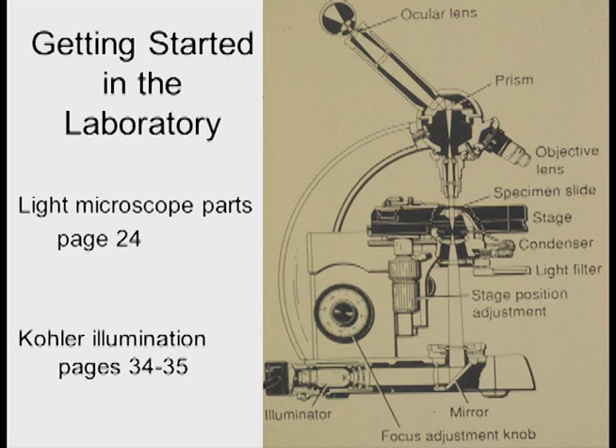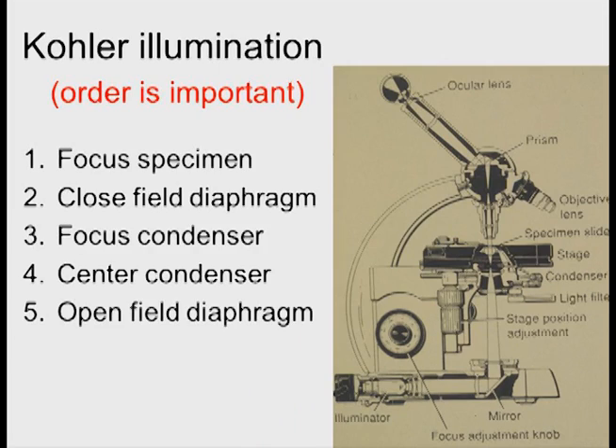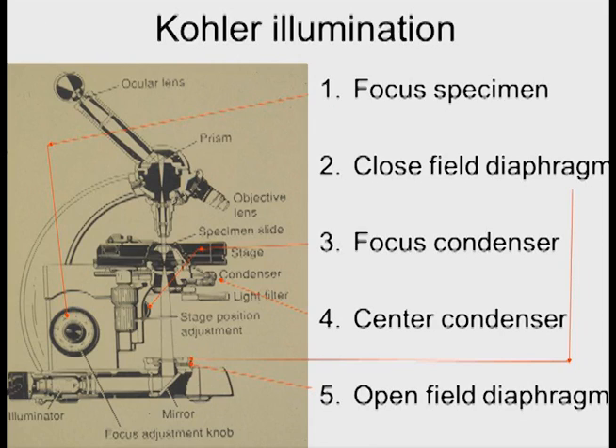Now getting started with microscopy, remember about Köhler illumination. There are five basic steps in Köhler illumination. The first thing you do is focus the specimen. Then you close the field diaphragm. Then you focus the condenser. You center the condenser. And then you open the field diaphragm again. So those are the different components of it.